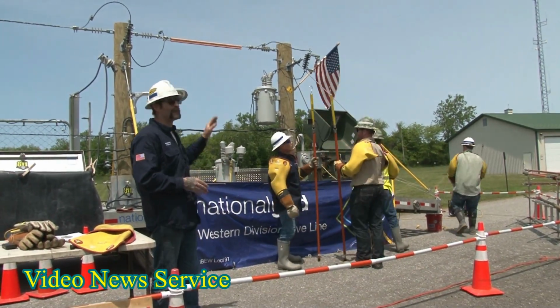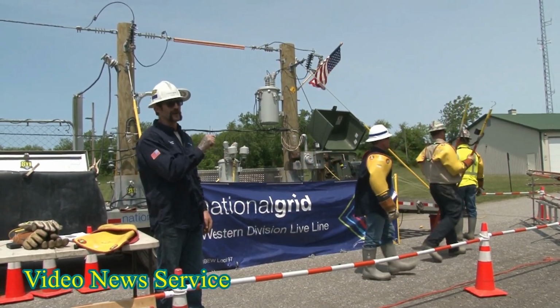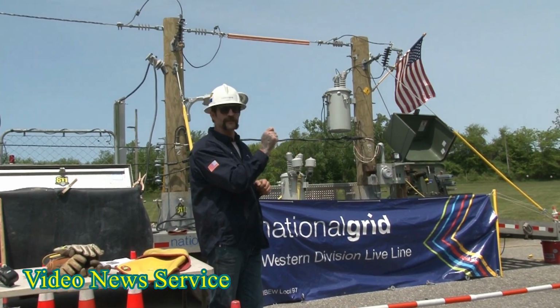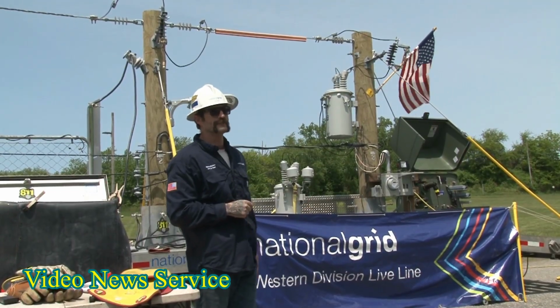So like I said, if you are going to wire a generator this way, ensure that your main breaker is off. If your main breaker is off, that electricity stops there. It'll keep your house energized, it won't go any farther. If your main breaker is on, it'll backfeed through that process and energize our lines and our equipment.